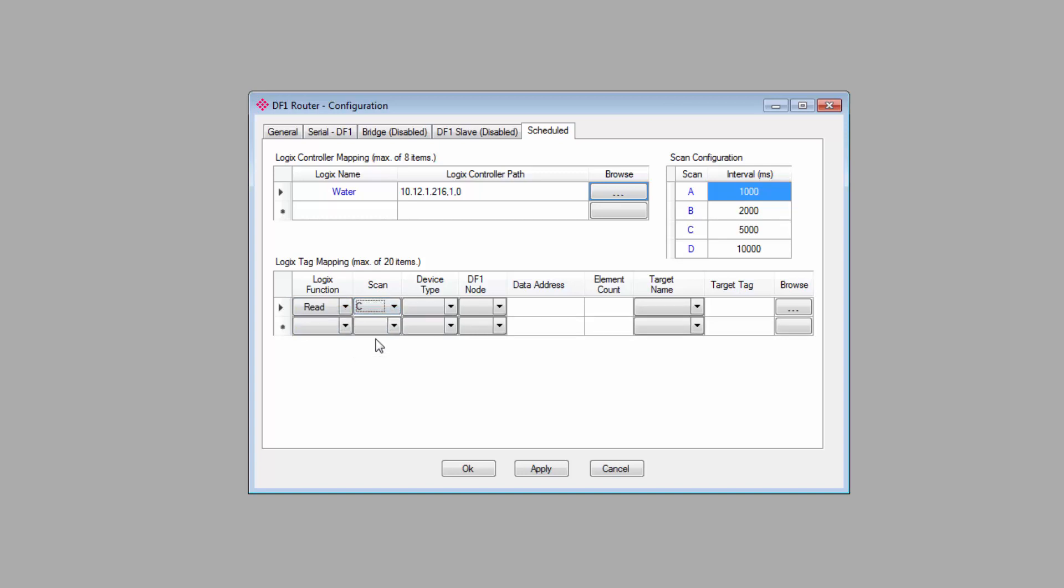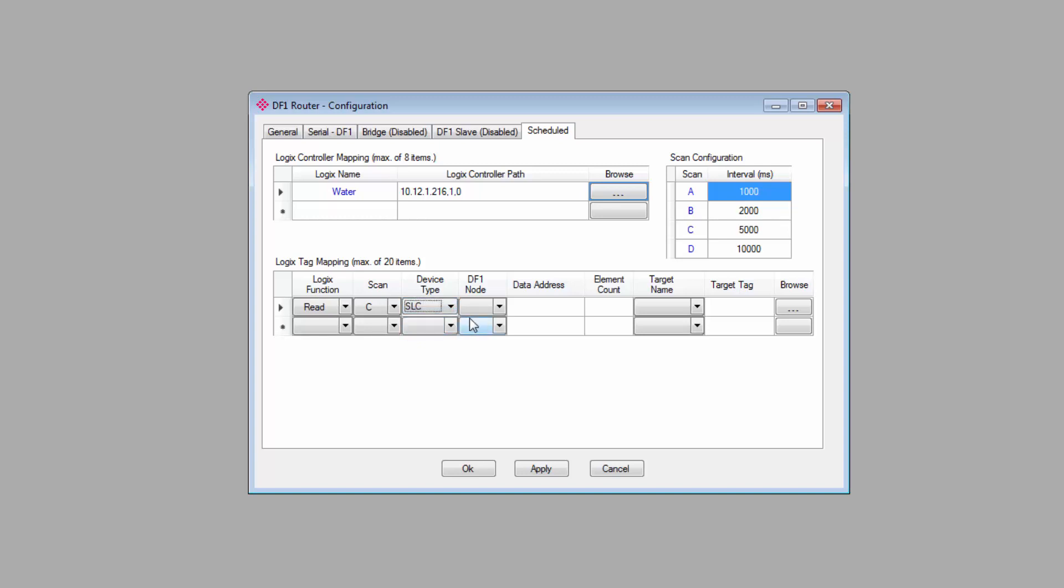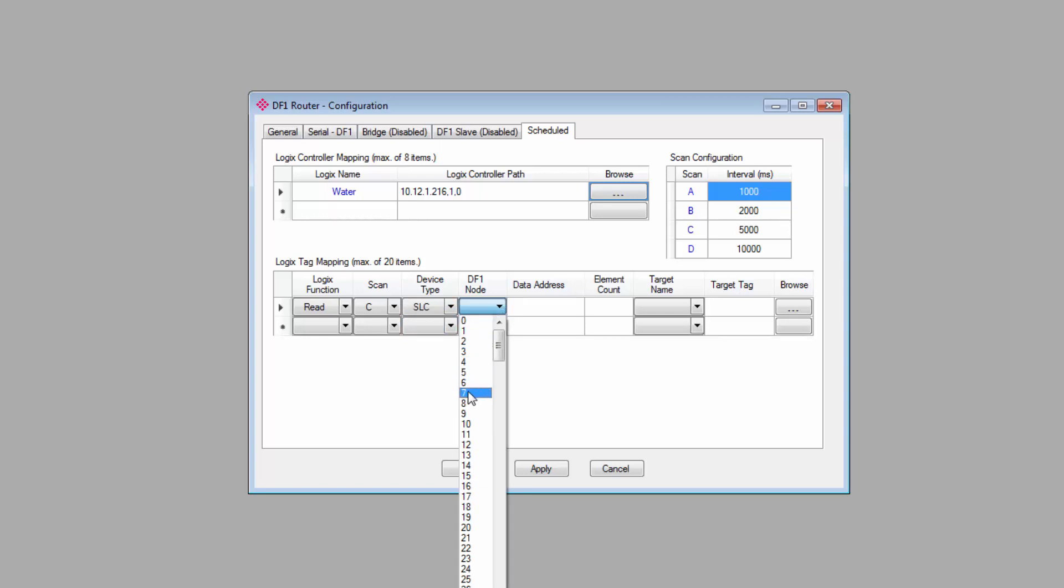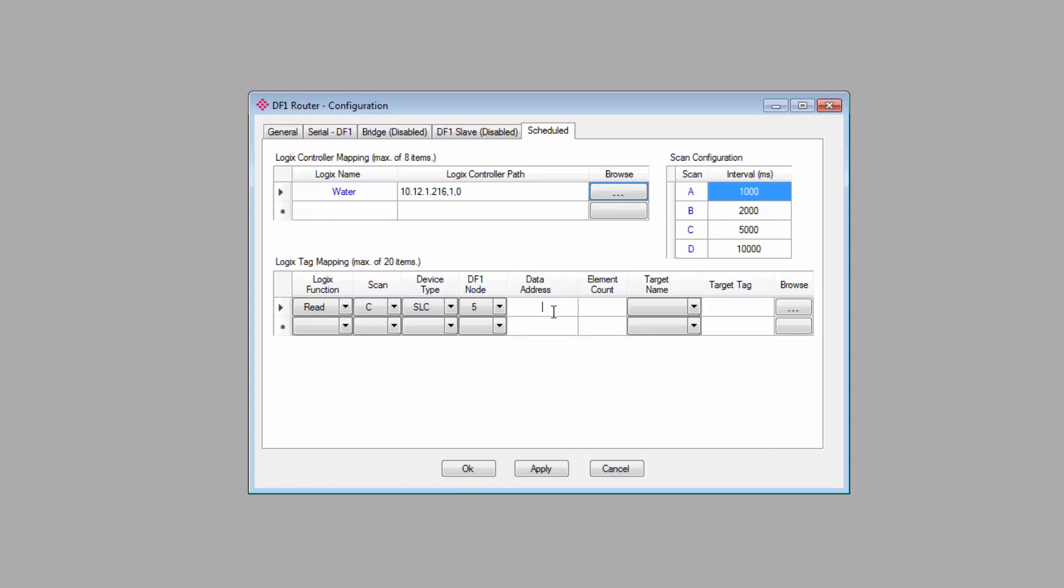Set the scan interval that you want to use. For device type, you would select either a SLC or PLC5, and in this instance, SLC will apply to all types of SLCs, as well as MicroLogix controllers. Next you would specify the destination node and data address. You can actually specify down to the word level in the DF1 device that you want to read or write to.